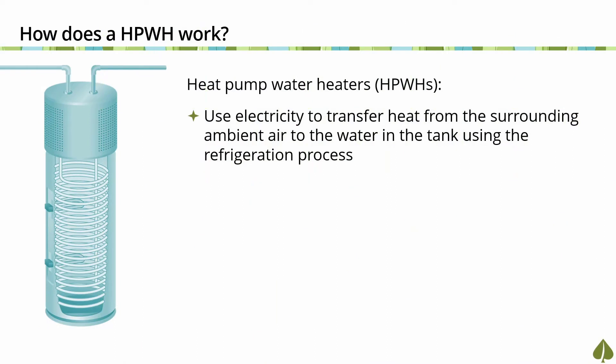A heat pump water heater works by using electricity to transfer heat from the surrounding ambient air to the water in the tank. This is called an air source heat pump or air to water heat pump. This process is similar to how an air conditioner works, only in reverse. Heat pumps extract heat from the surrounding ambient air and transfer it into water stored in the tank using the refrigeration process.